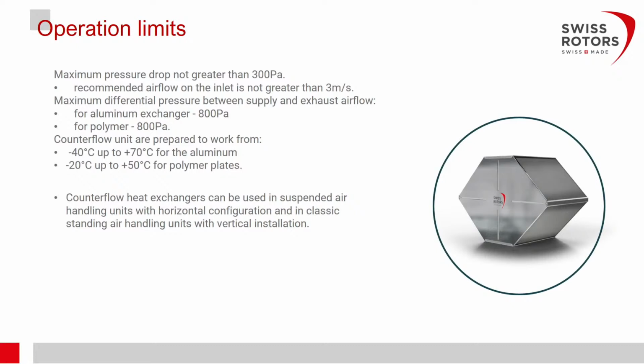Some operation limits of the heat exchangers. The maximum recommended, of course, we can have a bit higher, but recommended is 300 pascals, because with higher pressure drops, you will need to have higher capacity fans. That means higher power input. And recommended airspeed, air velocity, is up to 3 meters per second. The best is around 2 meters per second.